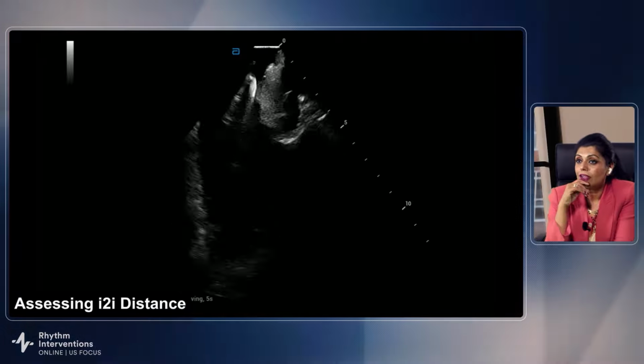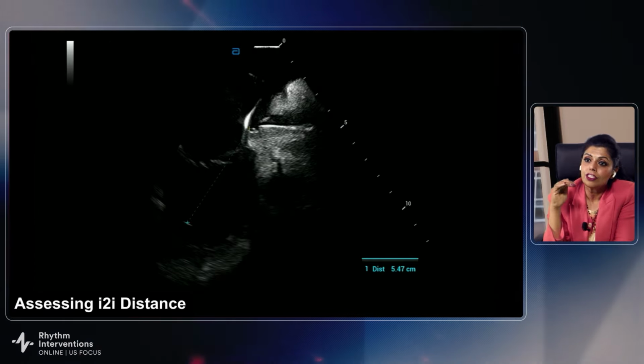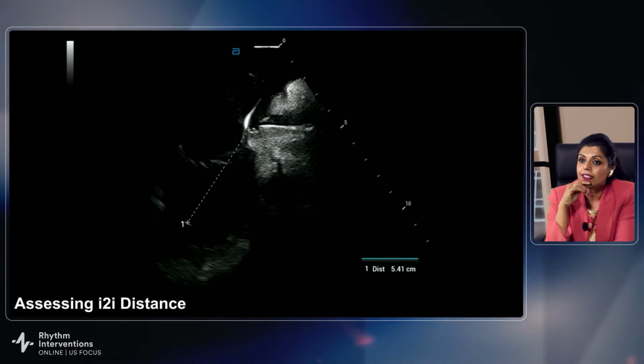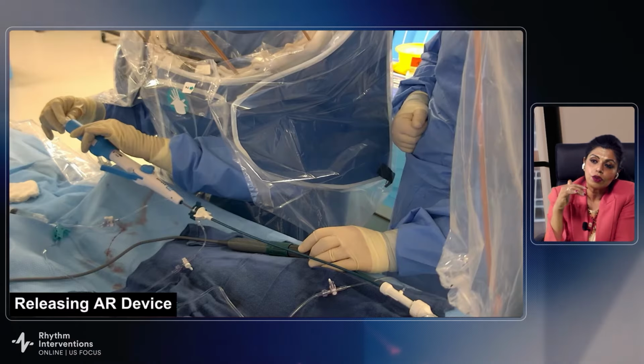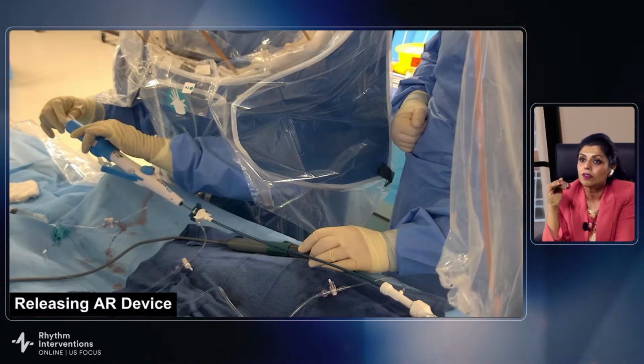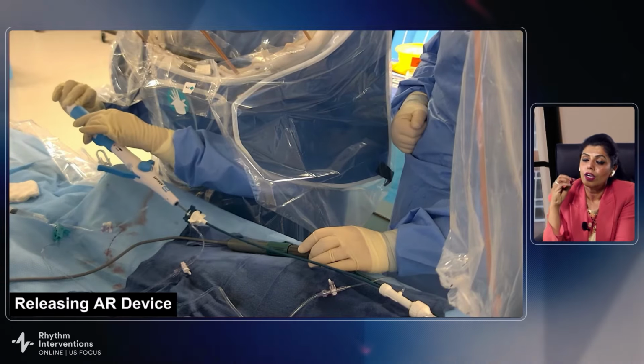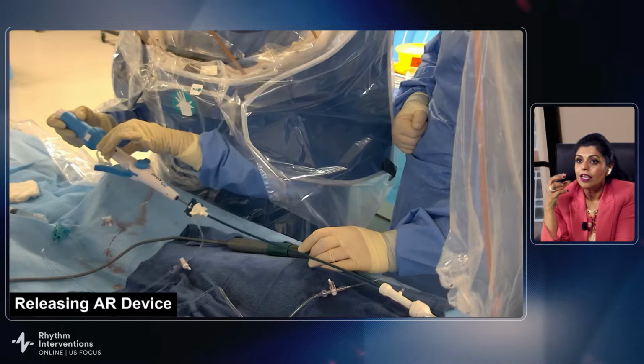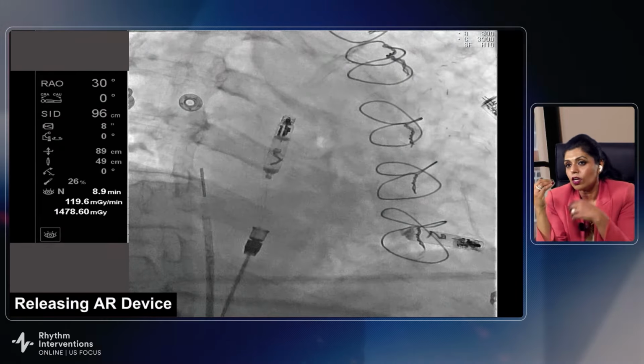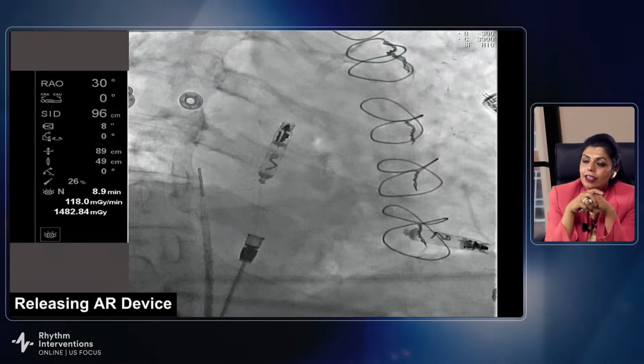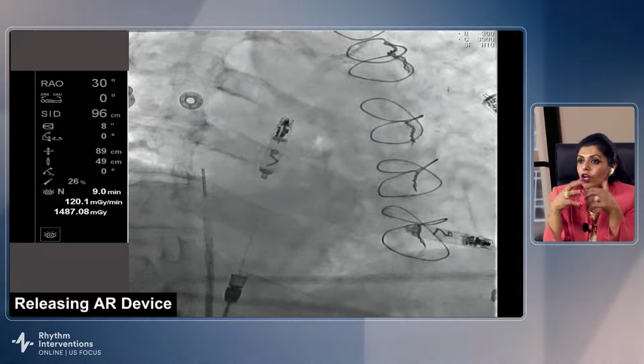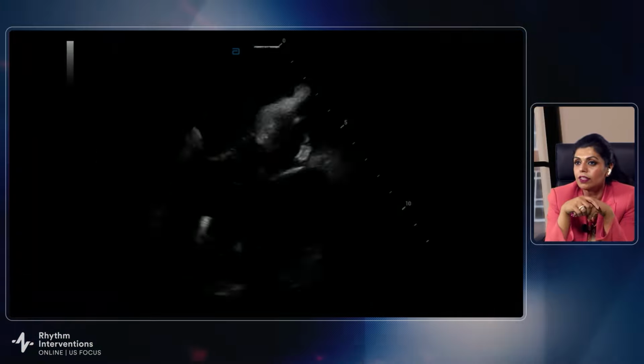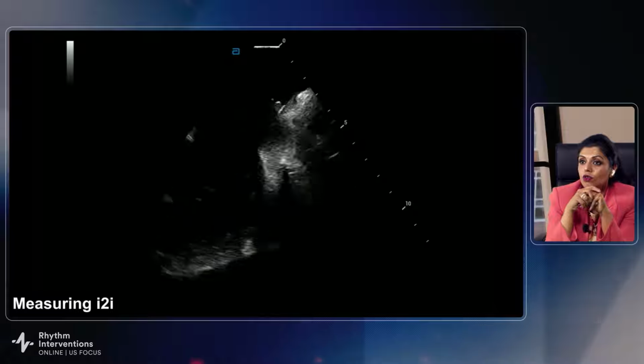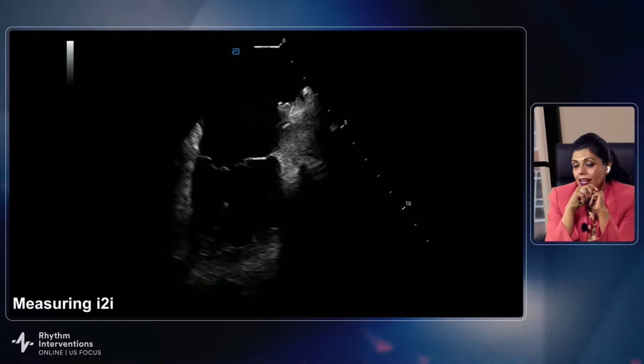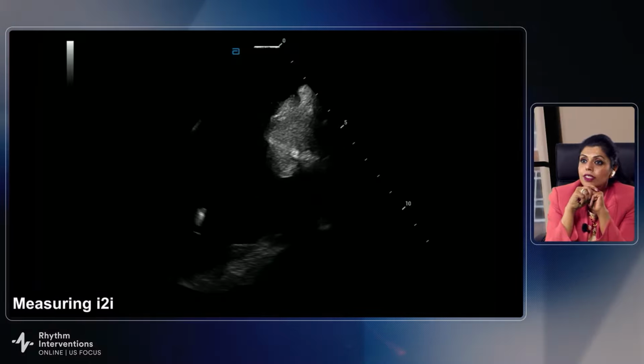Now, here what I'm doing is again checking the distance between the two devices. The implant-to-implant distance is one of the things that gives you good AV synchrony. If the devices are close to each other, there's less loss of battery, or there's more longevity in the battery when the devices are not too far apart, and better implant-to-implant communication.